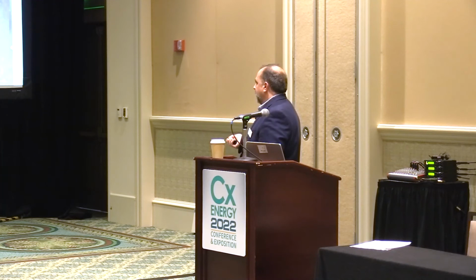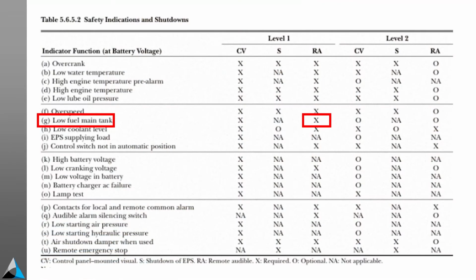Remote annunciators are one of the things we're always looking for. The low fuel alarm in the main tank has to annunciate on the generator's remote annunciator panel. During construction I saw they had the standard NFPA 110 panel. But when I came back for functional testing, the one that says low fuel had been taped over and labeled spare. I was not confident it would work when we tested it, and of course I was right.